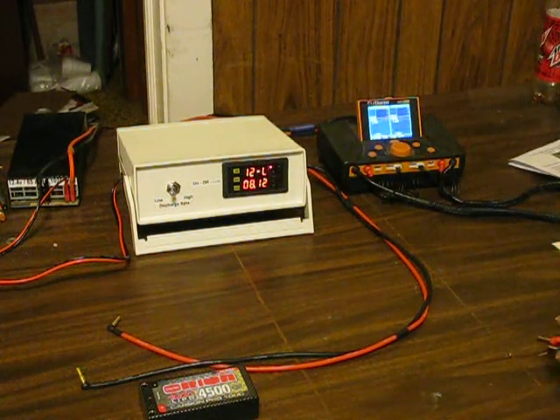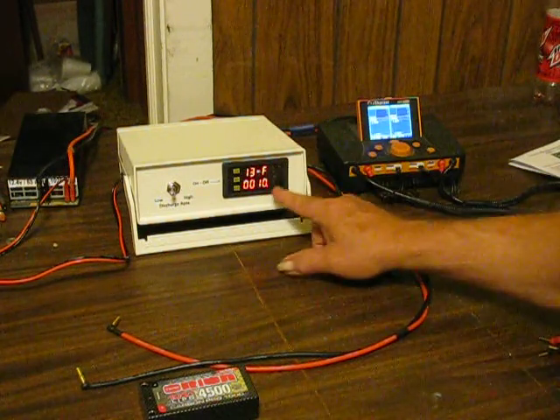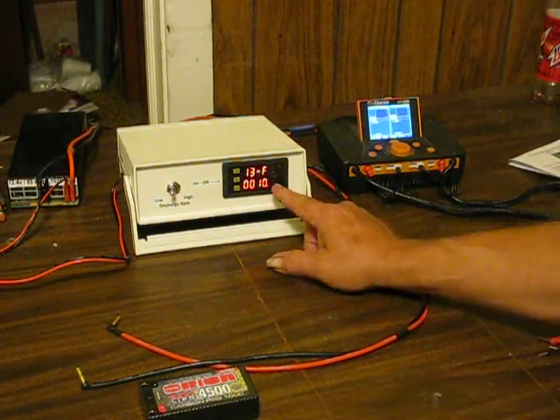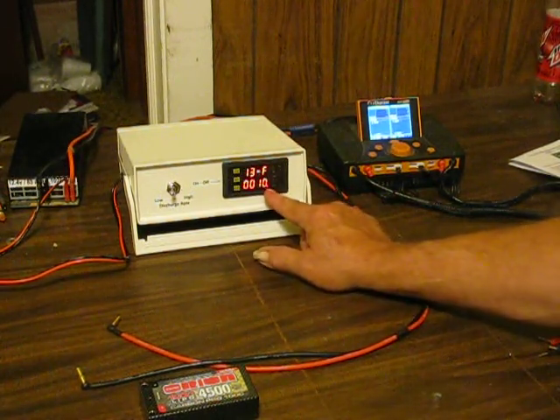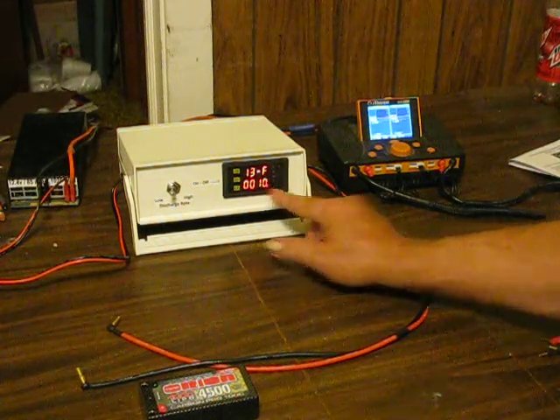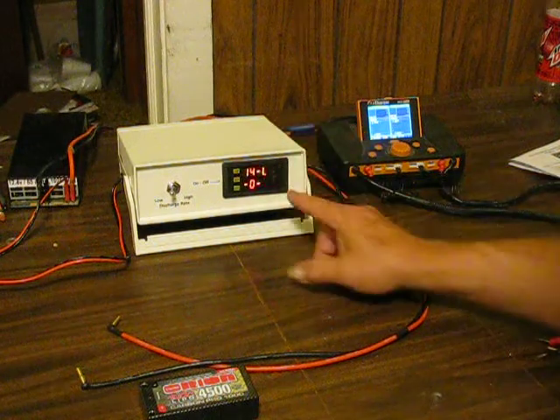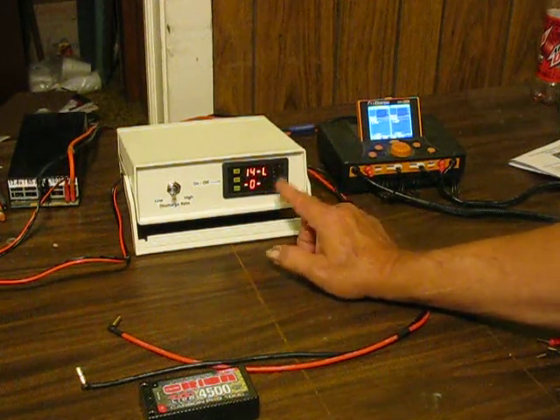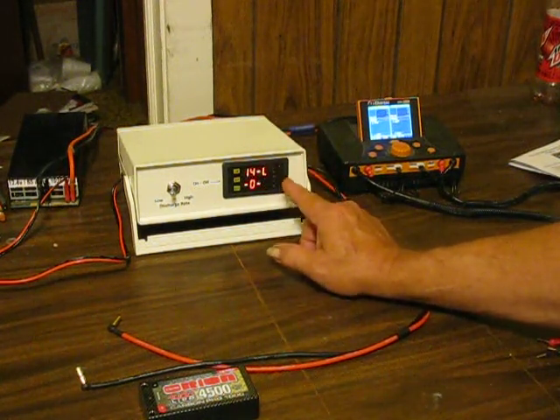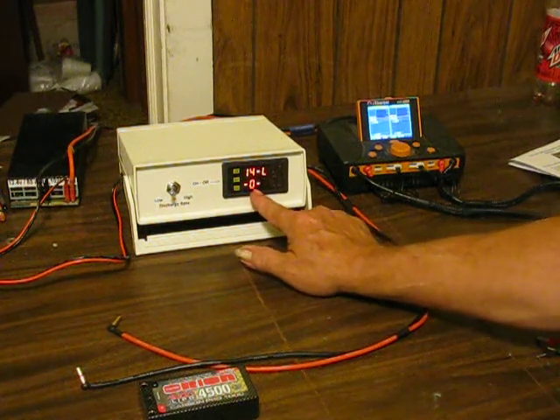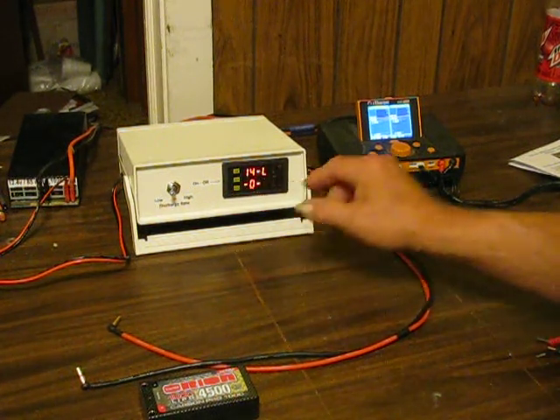We'll change that back later to a different figure. Step on to setting 13, which is calibration for the voltage. We want that number to be 10, which is usually right when you reset it. Next, setting 14 is the status of the relay in the unit. For right now, we want it set at 0. We'll change it later.